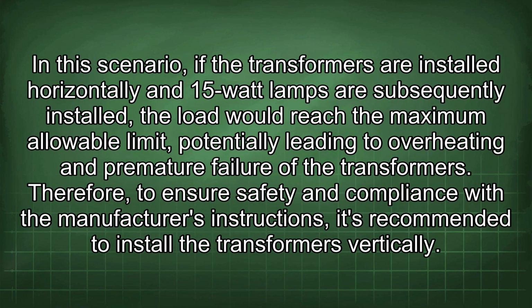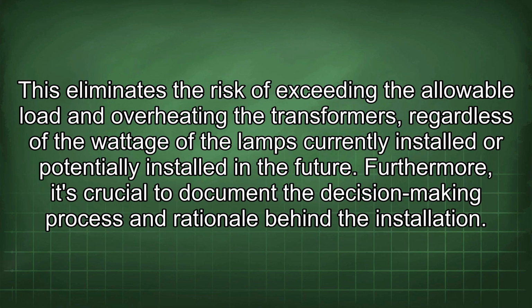In this scenario, if the transformers are installed horizontally and 15-watt lamps are subsequently installed, the load would reach the maximum allowable limit, potentially leading to overheating and premature failure of the transformers. Therefore, to ensure safety and compliance with the manufacturer's instructions, it's recommended to install the transformers vertically. This eliminates the risk of exceeding the allowable load and overheating the transformers, regardless of the wattage of the lamps currently installed or potentially installed in the future. Furthermore, it's crucial to document the decision-making process and rationale behind the installation.